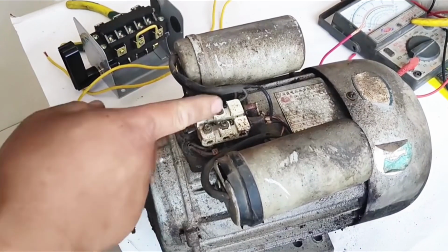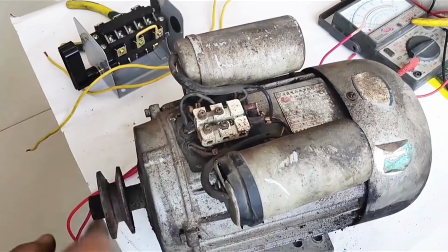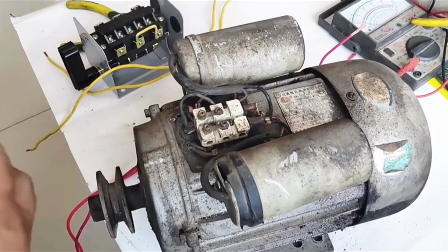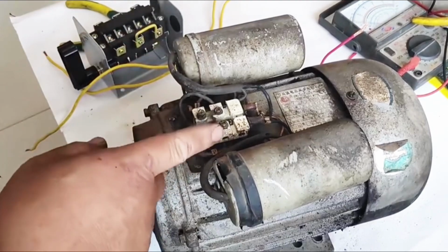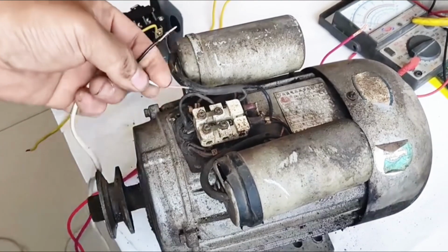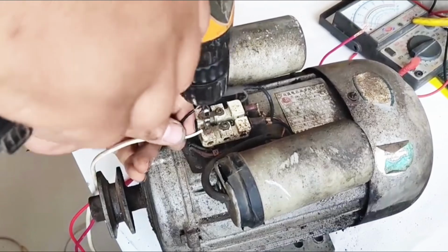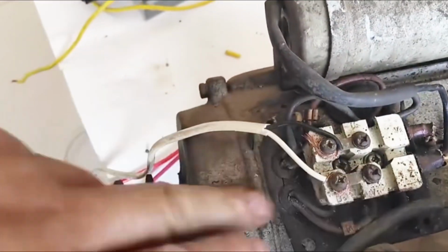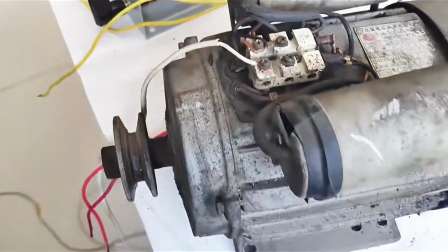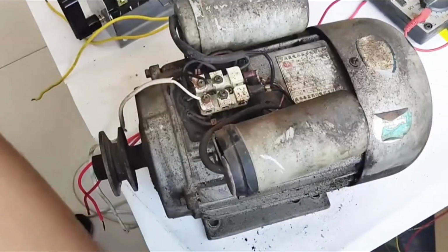To make the motor run, there must be a rotating magnetic field, so what to do? We can add another coil in the motor, that is, what we call the auxiliary winding, and connect a capacitor in series with that coil, so that the currents flowing through the two coils produce an angle, and the magnetic field can rotate after the power is turned on. This is where we add the start capacitor.